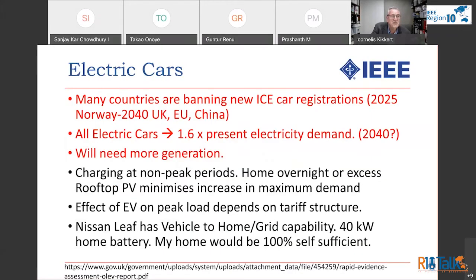Many countries are banning internal combustion car registrations. If all cars are electrical, that will increase the demand by 1.6 times, and that may be in 2040. We'll need more generation, but charging at non-peak periods, overnight or with excess rooftop, will minimize the increase in maximum demand. The way that is done, of course, will depend on the load structure. A Nissan Leaf at the moment, for instance, has got vehicle-to-home grid capability. So that's equivalent to a 40 kilowatt hour home battery. My home would then be 100% self-sufficient.